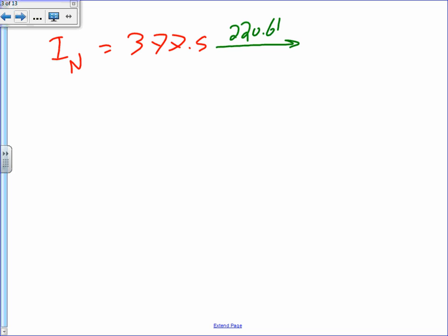Now here's where you can, guys, here's where I neutral was 377.5. Do you see the I neutral, 377.5? Gentlemen, from here I can derate more, based on 220.61. The first 200, what do you do with them?